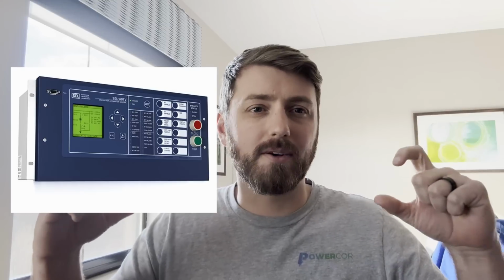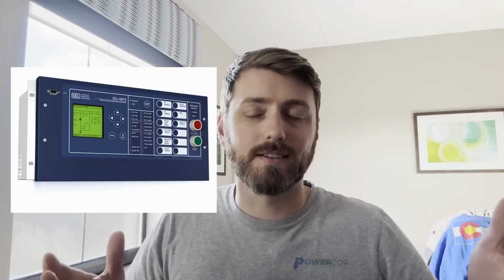Well, we just sort of all decided universally they're either going to be bigger cases, like the SEL 751 and GE 8 series, where they're substantially larger than the old FTs were, or the substation style that's very wide, mounted on a 19-inch server rack in the control house. That's really popular too. But we still had a need to isolate our I/O, to isolate our trip circuits, to short CT circuits, all of the same problems that we had isolating the electromechanical relays in these FT cases. Well, we still have those now.